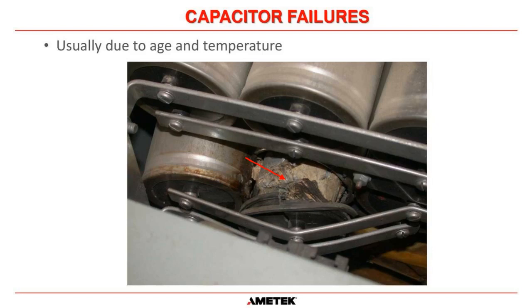And a DC capacitor is very similar to a short-term battery. It has electrolyte inside of it, and they are sealed, and that electrolyte is supposed to remain in the capacitor at all times during its life. But what happens is, if the capacitor is heated up above its normal temperature range, that electrolyte within that capacitor will eventually dry out, because each capacitor has a valve on the top of the capacitor to let pressure out. And in letting pressure out, it will let some of the moisture within that electrolyte out.